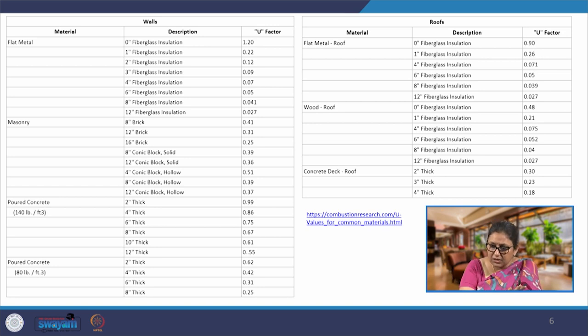So if you look at databases, there are a lot of databases which are available for India. The database that we are using for most of the commonly available materials is available in ECBC, energy conservation building code, and there is an annexure which is there. You can get the U values from there. And depending upon the areas that we have, the surface areas for each different type of material, we can calculate how much saving is going to happen over a period of time. So we can calculate it on a yearly basis, on a daily basis, it will change. For more accurate results, as I had said earlier also and I am repeating, we will have to do whole building simulation using simulation tools, simulation software, which will give us all of this together in one single figure.